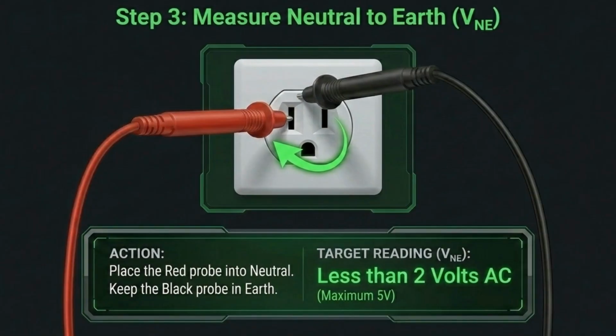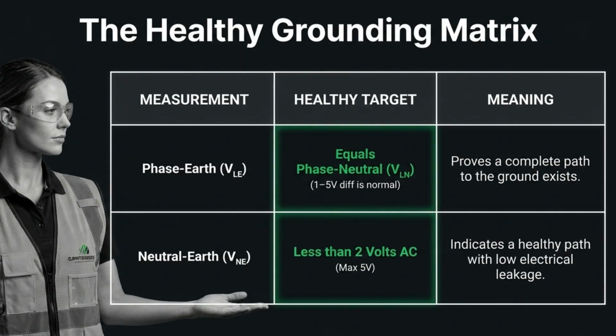Step 3. Measure neutral to earth. Place the red probe into neutral and keep the black probe in earth. The target reading, VNE, should be less than 2 volts AC with a maximum of 5 volts. This is the healthy grounding matrix.